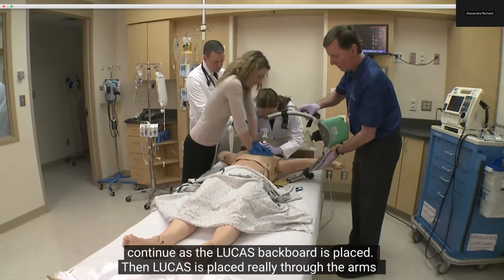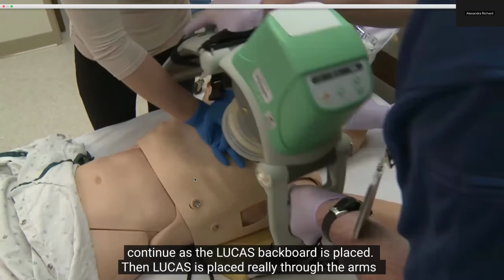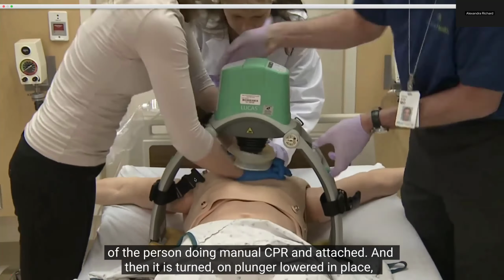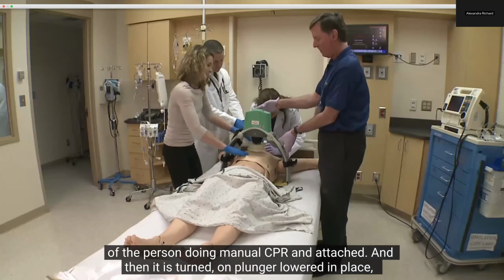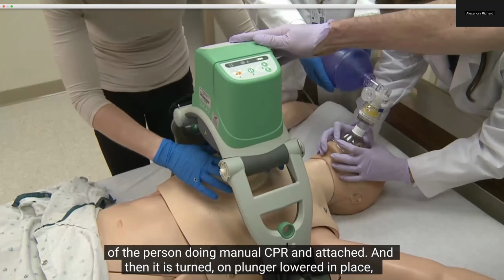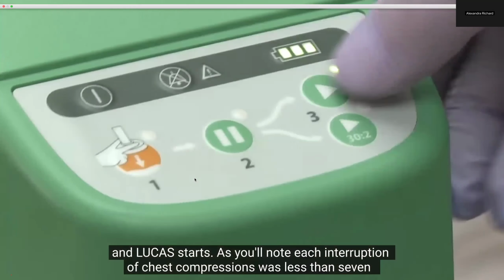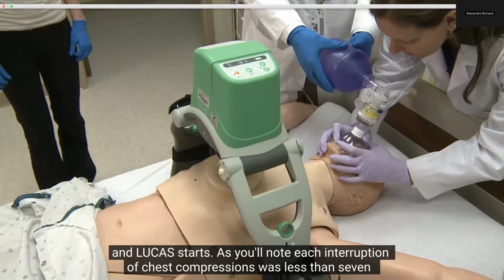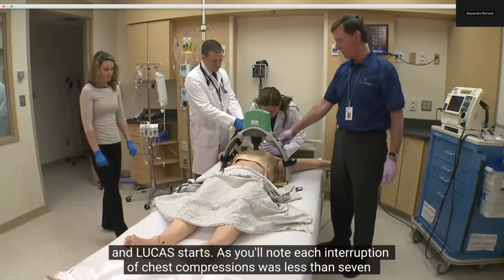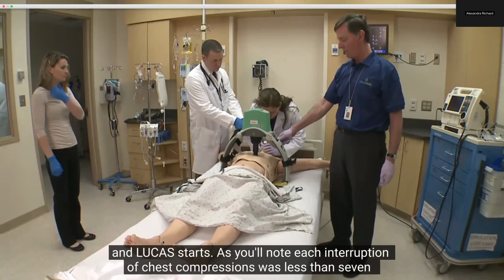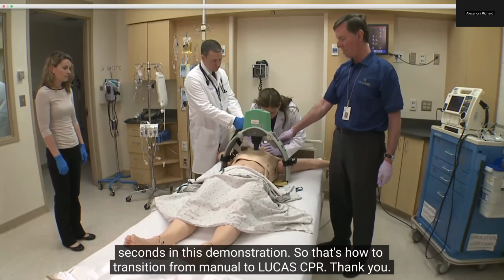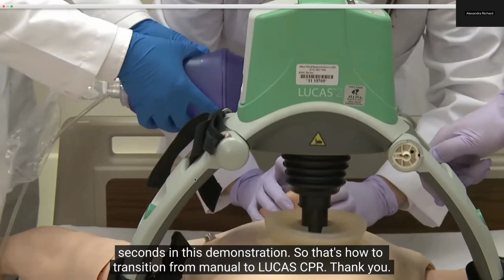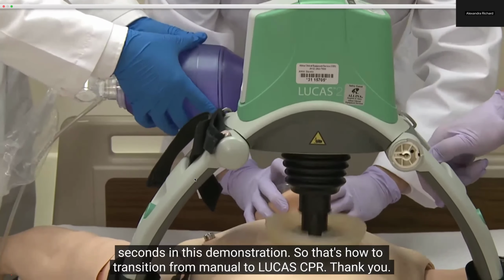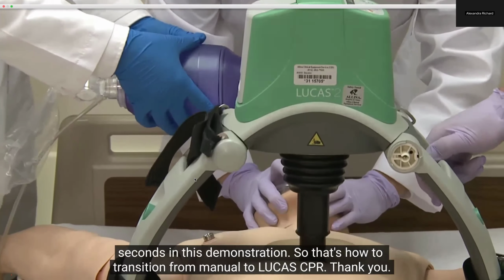Then Lucas is placed through the arms of the person doing manual CPR and attached, and then it is turned on, plunger lowered in place, and Lucas starts. As you'll note, each interruption of chest compressions was less than 7 seconds in this demonstration. So that's how to transition from manual to Lucas CPR. Thank you.